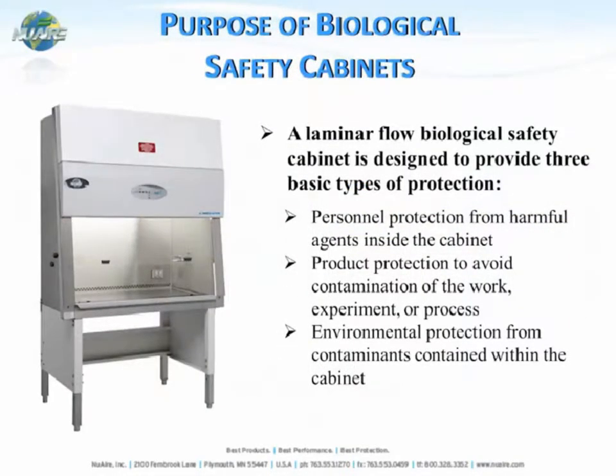To begin, we want to look at what the purpose of a biological safety cabinet is. It is designed to provide three basic types of protection: personnel protection from harmful agents inside the cabinet, product protection to avoid any contamination of your work or experiment, and environmental protection from the contaminants contained within the cabinet.